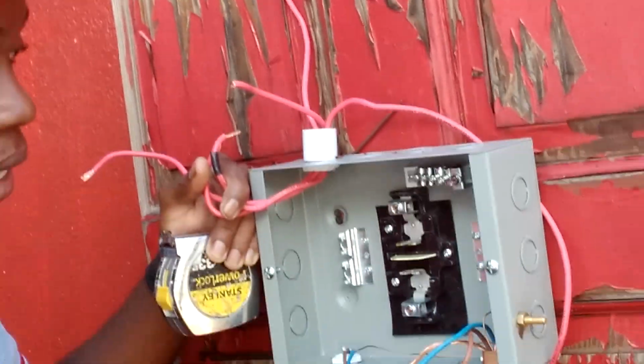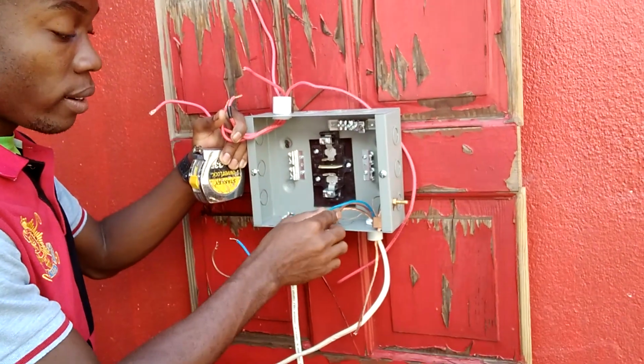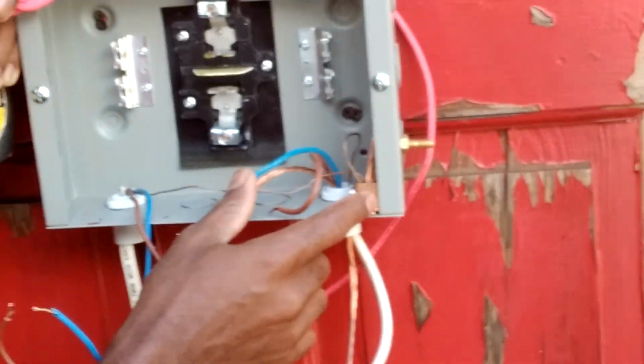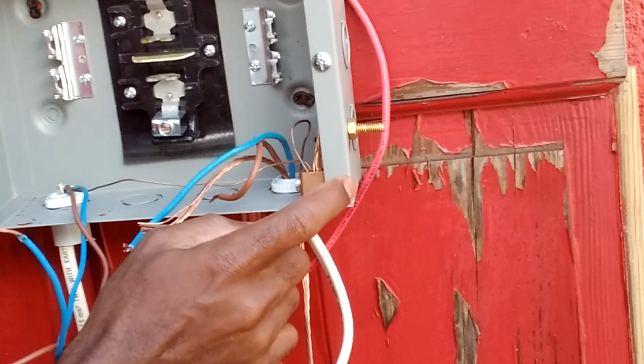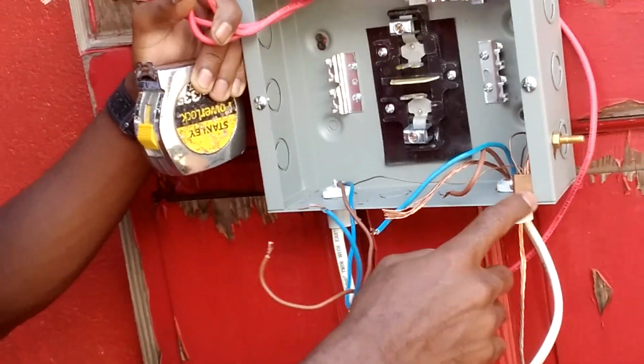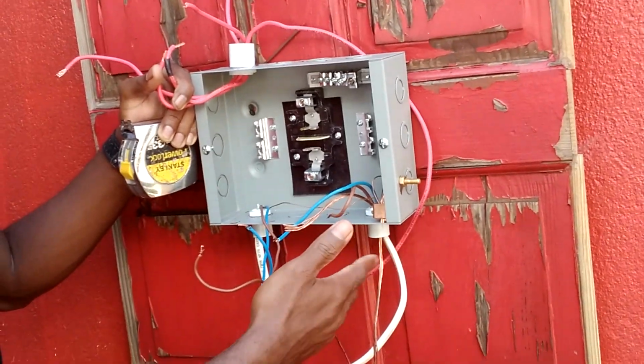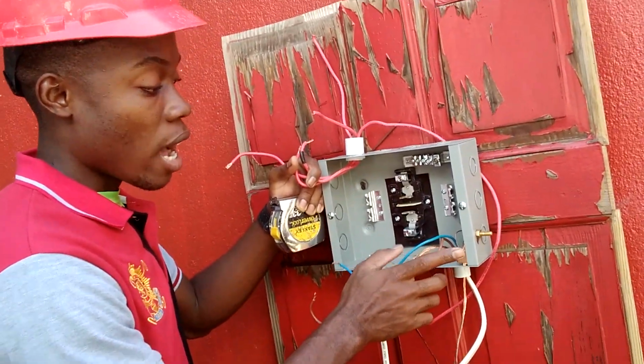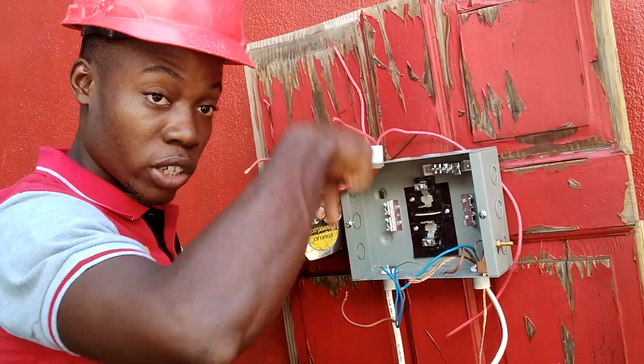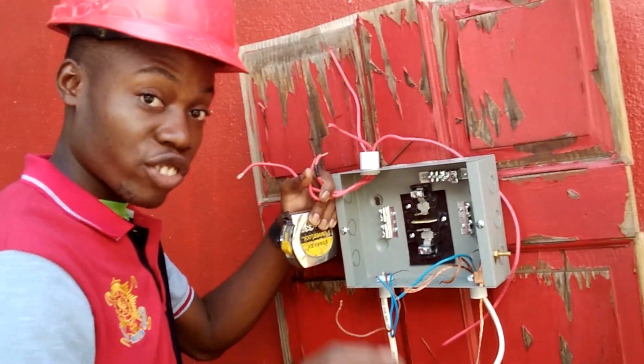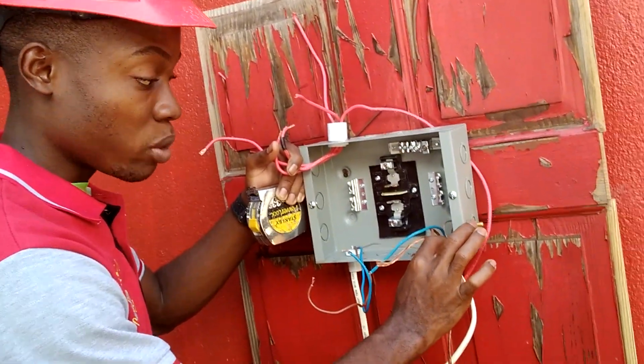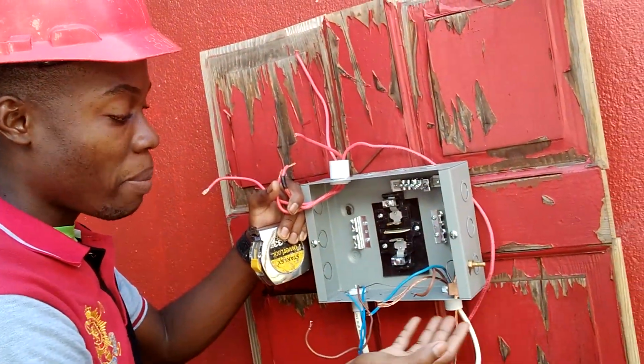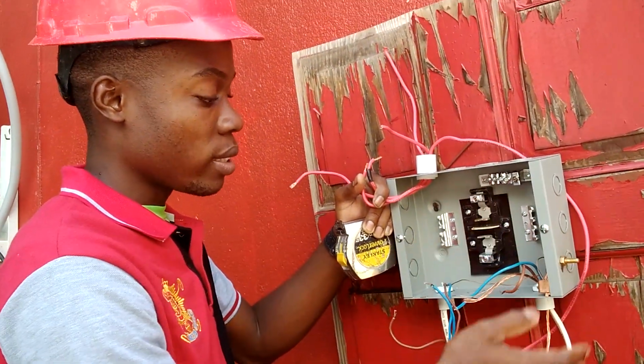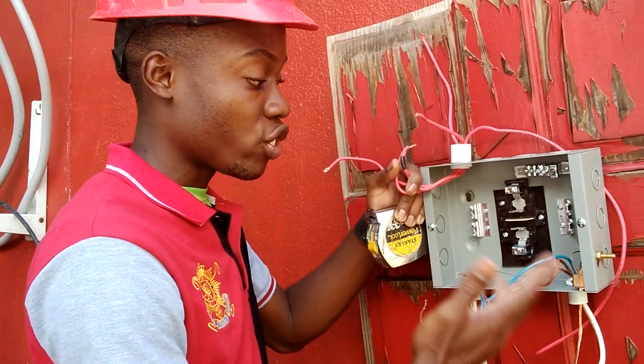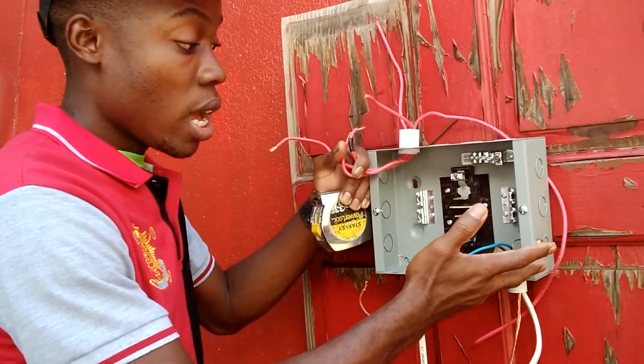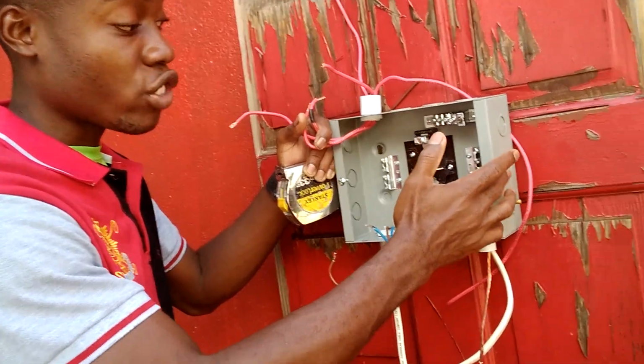This gold, or copper looking, thing here is called an earth lug. It is for the protection of the panel, and I've already pre-mounted it so this video can move a little quicker. This is where all the earth wire goes, that goes into the ground. Many of you have seen that little copper rod driven into the ground - this is where the connection for it comes to. What it does is protect the panel casing. Say for instance, if a live wire should get charred and touch the metal of the box, then it protects you from getting an electrical shock.